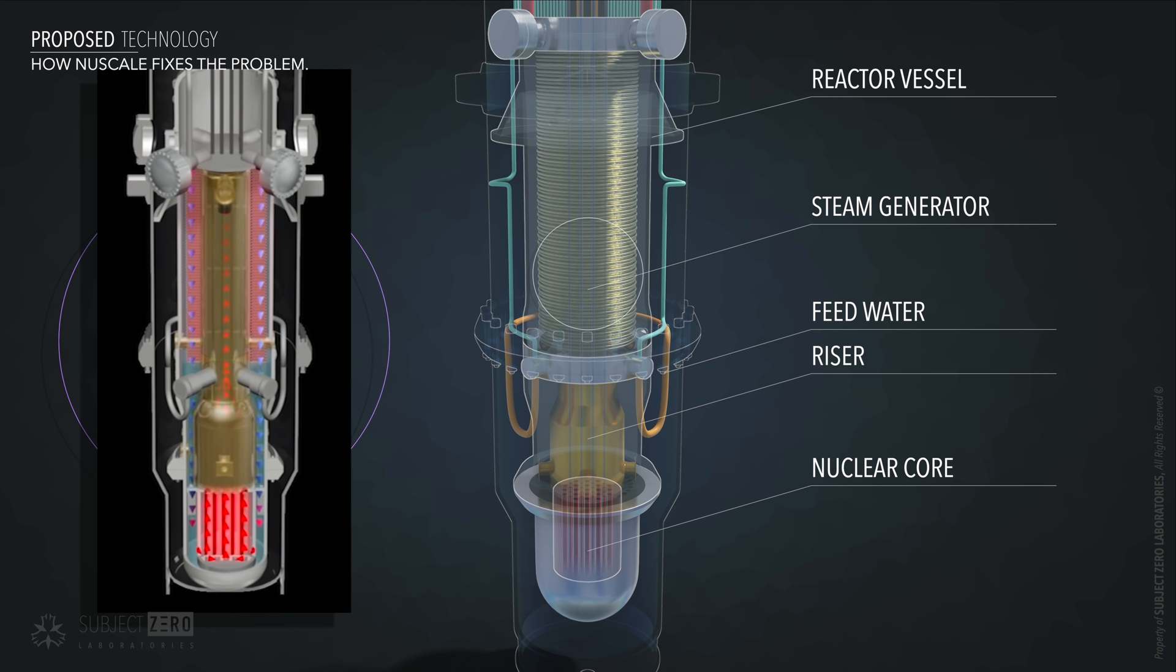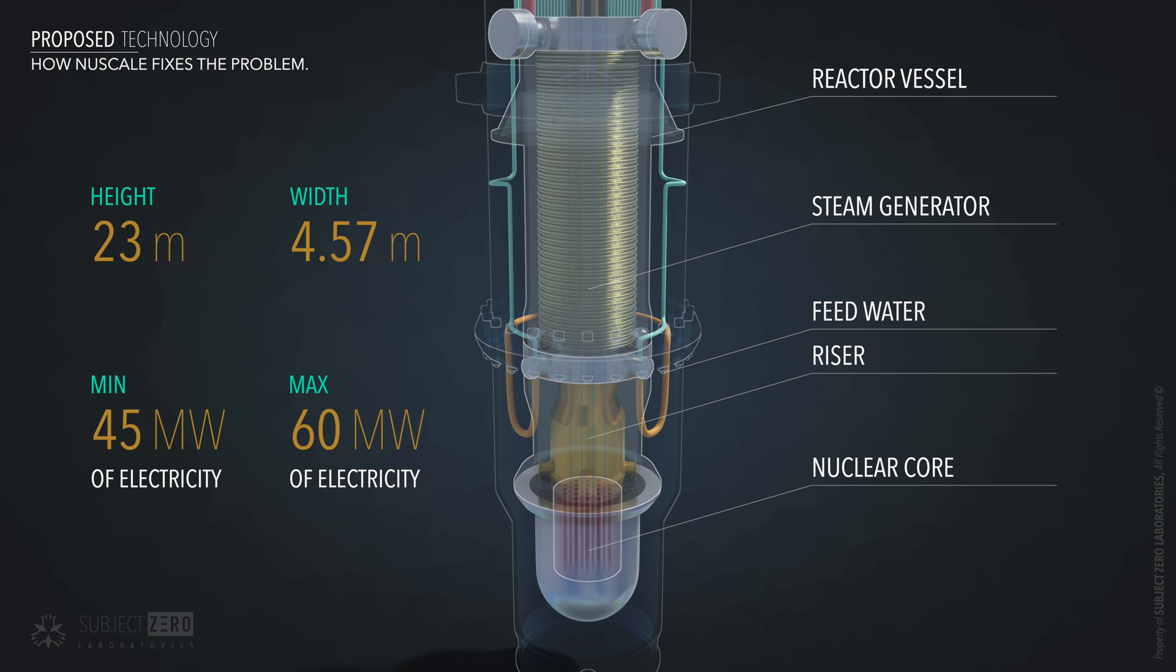Steam generated during this process goes up the pipes all the way to the generator, moving the turbine, producing electricity. The steam is condensed, turned into liquid, and pumped back into the reactor. All of this happens inside a containment vessel that is about 23 meters tall and 4.57 meters wide and can output between 45 and 60 megawatts of electricity.